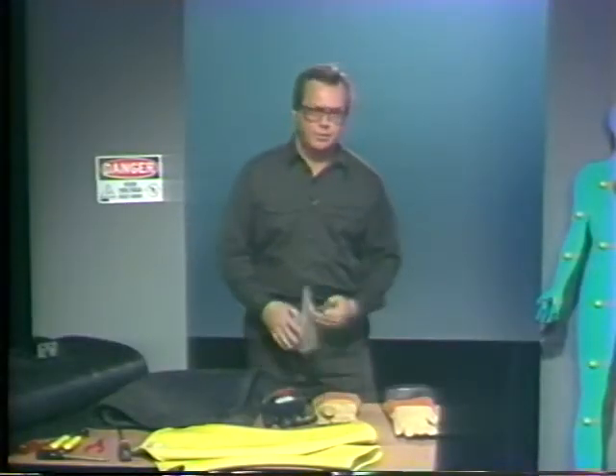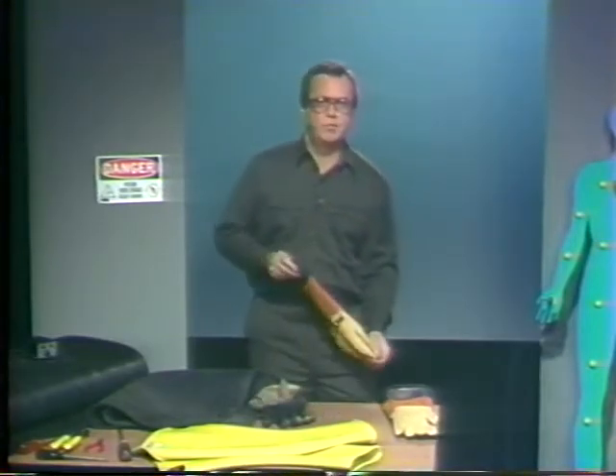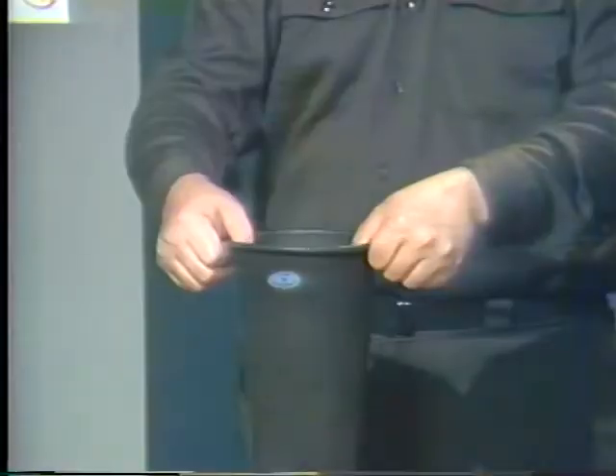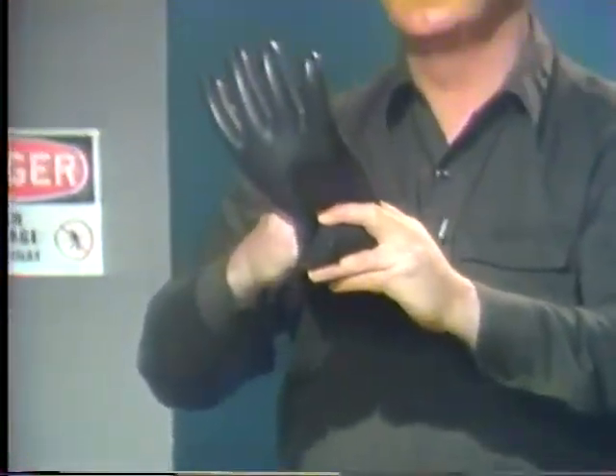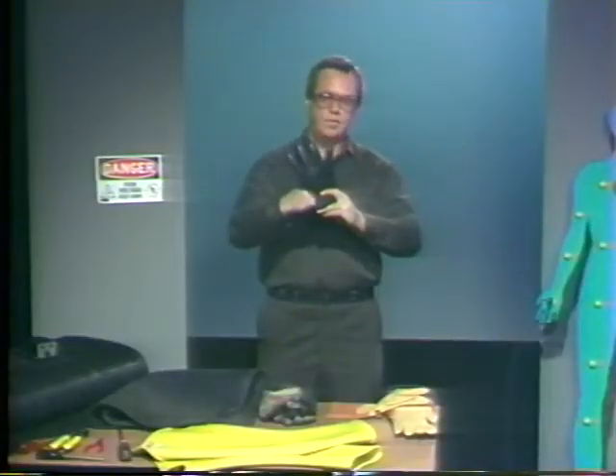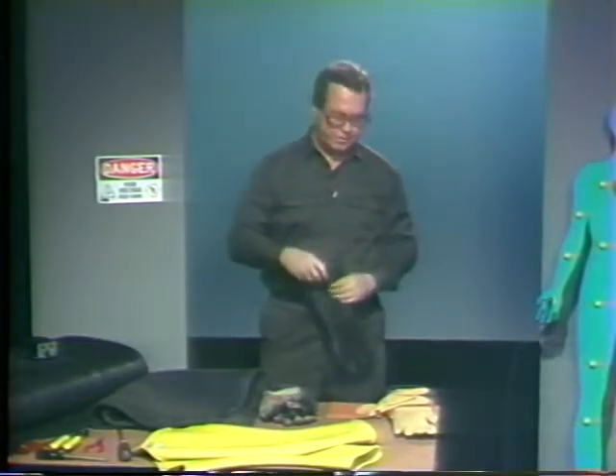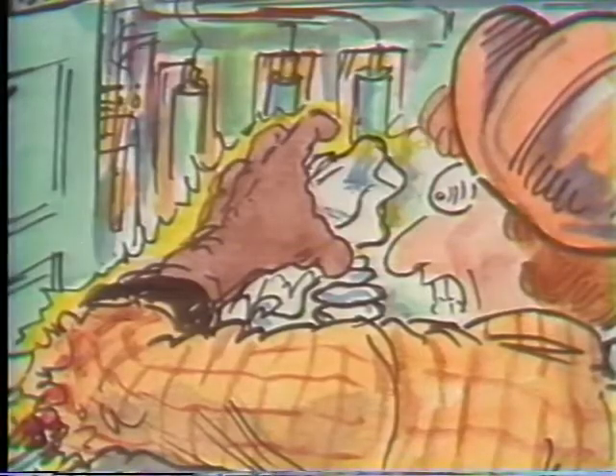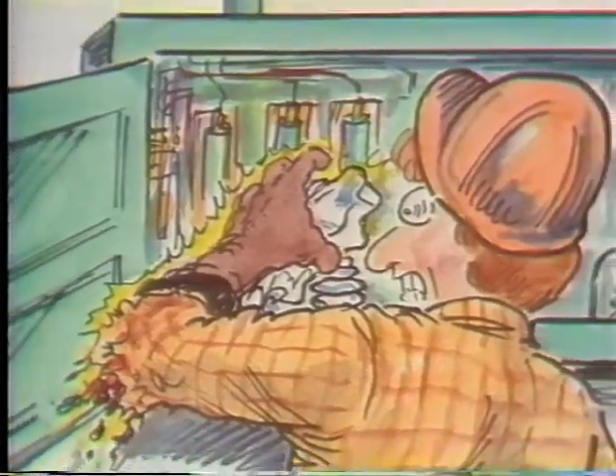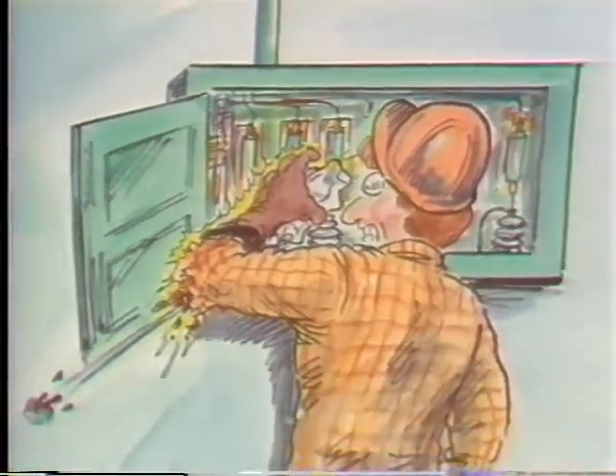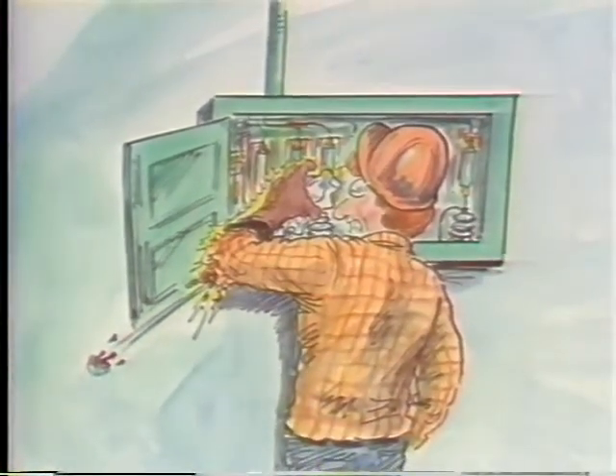To look for small punctures, you twirl the glove to inflate it, something like this. Then listen and feel for any leaks. If you find any holes or damage, turn in the gloves and get a new pair. Even a pinhole leak can make a difference. A small hole in a fingertip left a slightly larger hole in this man's elbow when it got near the grounded fuse box. That's why leather covers are important. The leather's there to prevent small cuts and punctures that can destroy the insulating properties of the glove.